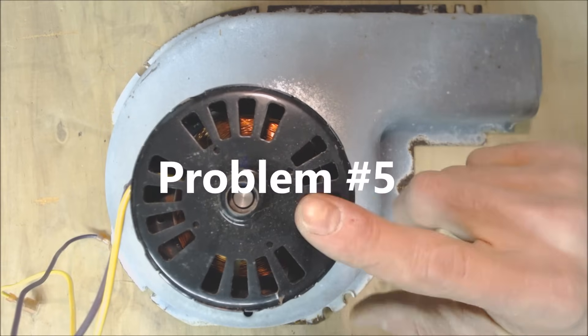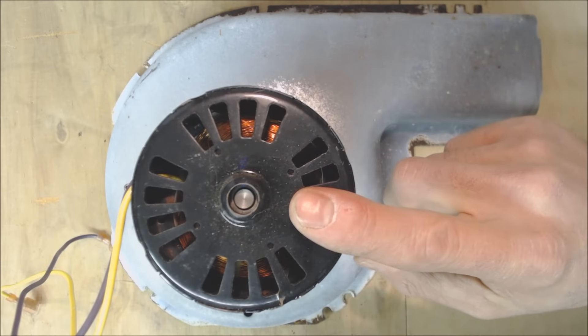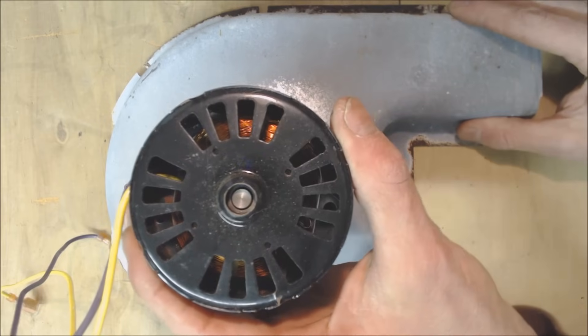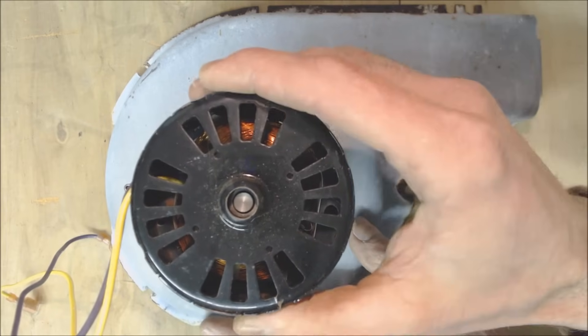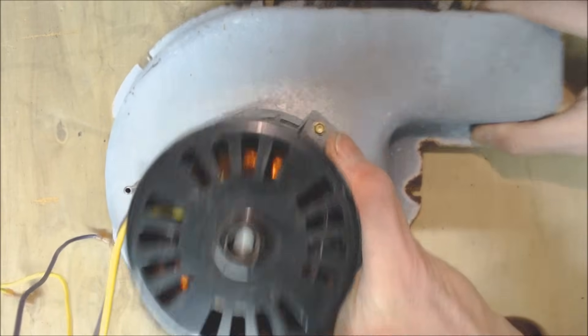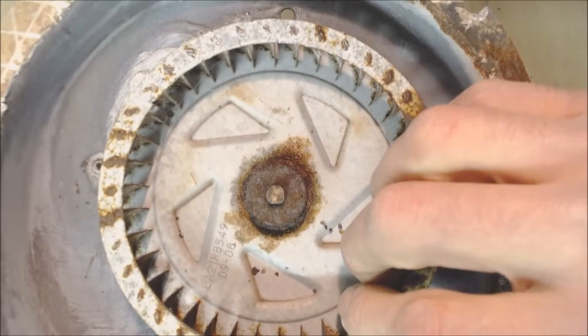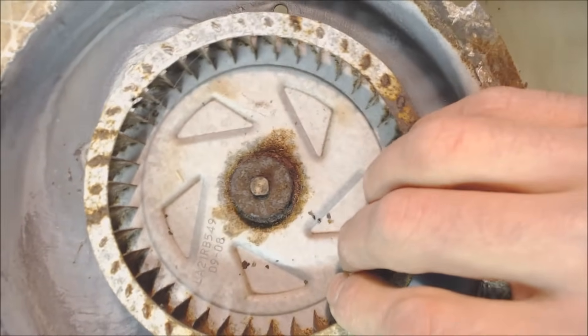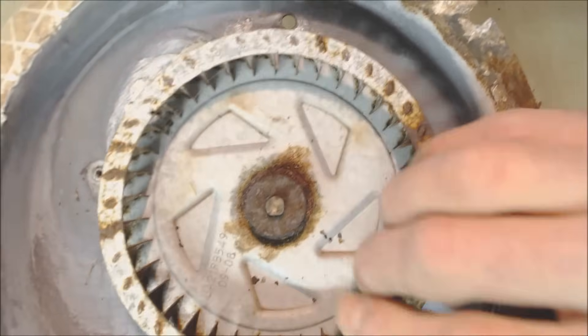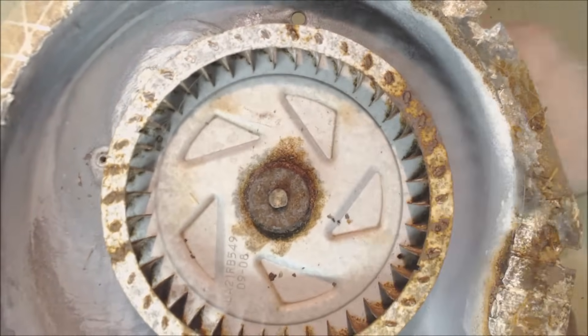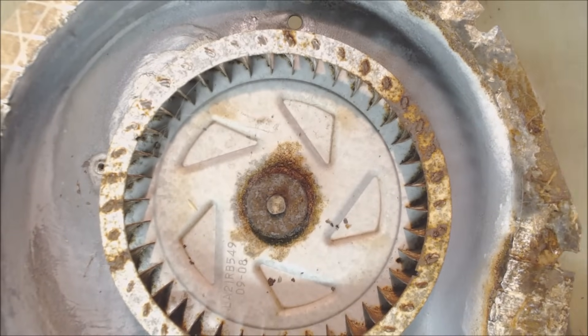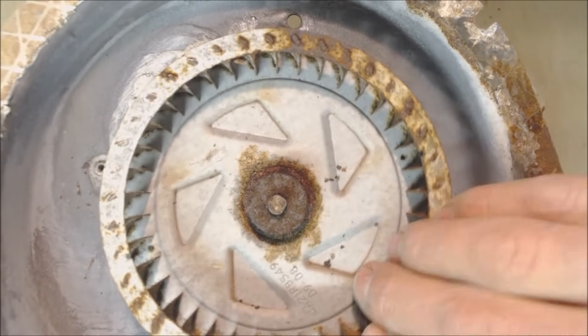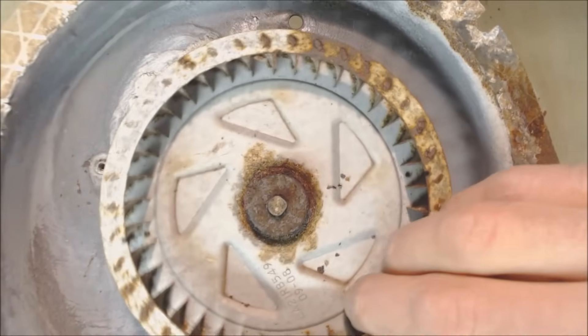This is problem number five and this inducer motor was out of a package unit and you can see that this one has some play in it. It actually moves back and forth like this and the problem with that was that the inducer wheel was binding on the edge by the heat exchanger and that was a problem and then the inducer motor was not turning on. It was actually just getting stuck. So that's something that could happen or debris could be stuck in here maybe from a bird's nest and that's not allowing the motor to turn on.